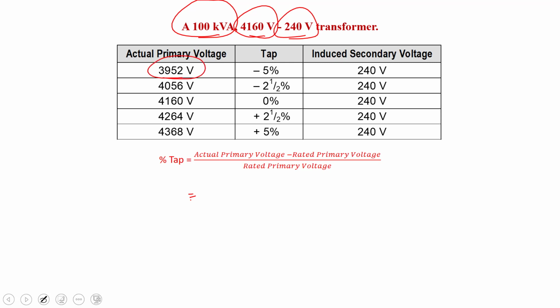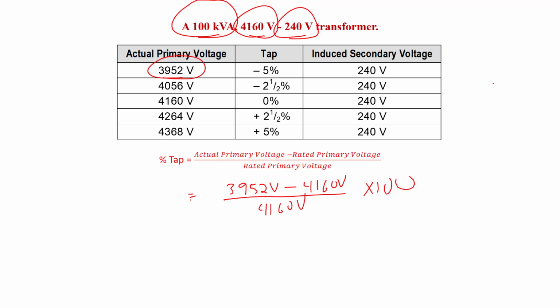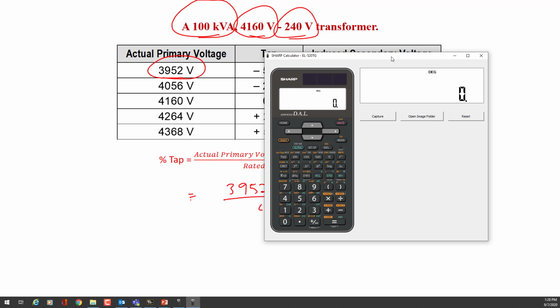So let's say that I measure 3,952 volts. So actual primary voltage is 3,952 volts. I subtract the rated primary voltage, which is 4160, and then I divide it by the rated primary voltage of 4160. And then you can times that by 100. All right, so let's see what that would look like. I'm going to grab my calculator here, clear it. So I'm going to move this over a bit for us.